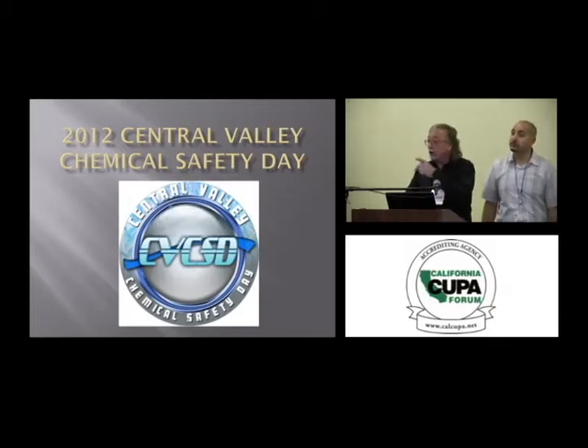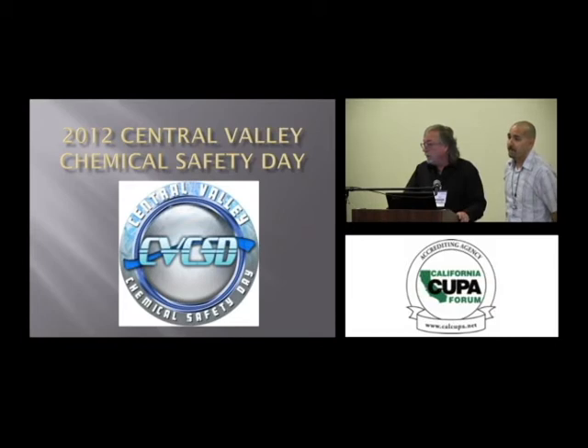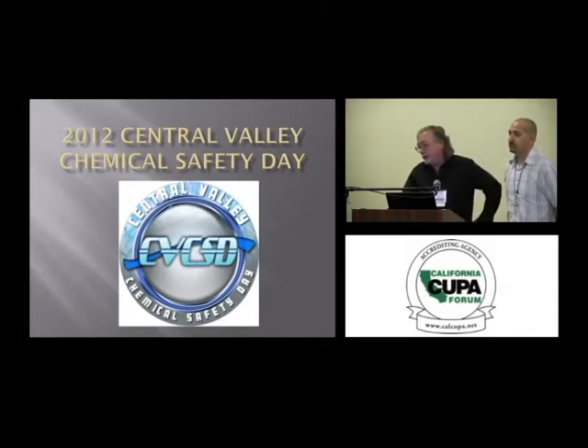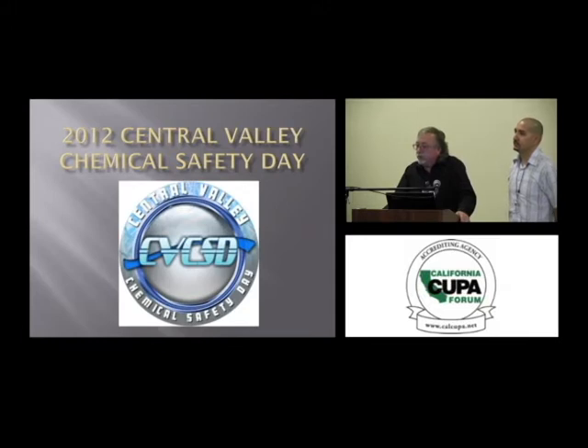Yeah, go ahead. The IIAR guidelines are for refrigeration systems. What about ammonia in power plants where they're using 19% ammonia for the NOx cut down? Yeah. Basically, when you're looking at the ammonia injection grids, the equipment's the same. I mean, you don't have the compressors, but where we run into most of the problems at those facilities is piping components, connections, labeling, safeties, things like that. But yeah, it's the same thought process. You're just looking at less rotating equipment.